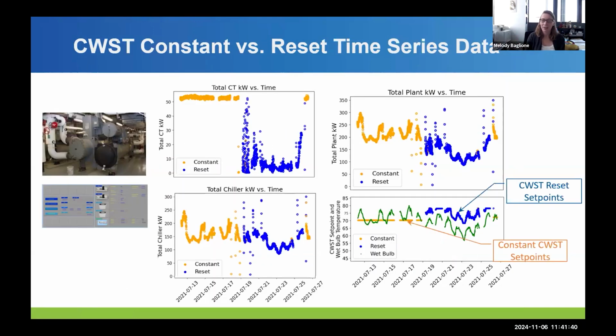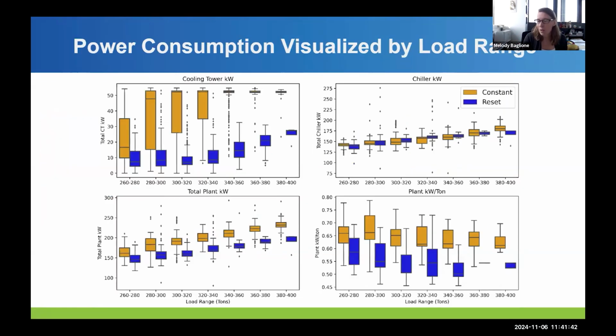And then the students plotted the actual data using Python and box and whisker plots for different load ranges, and showed that under all load conditions, the reset temperature, especially for the cooling tower power, but also for the plant kilowatt per ton, achieved energy savings.